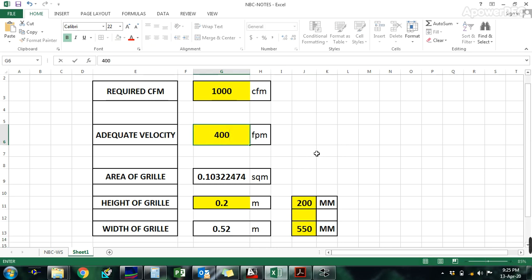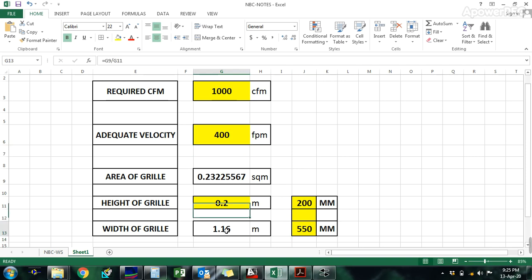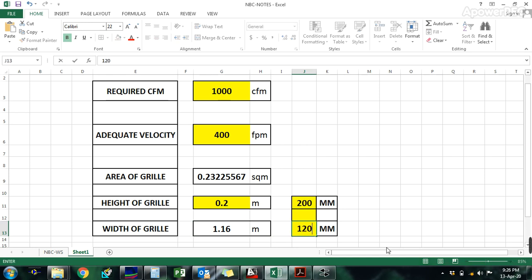At 400 FPM, the size is bigger — the width comes to 1.16, approximately 1.2, meaning 1200mm. So the size is more at lower velocity.